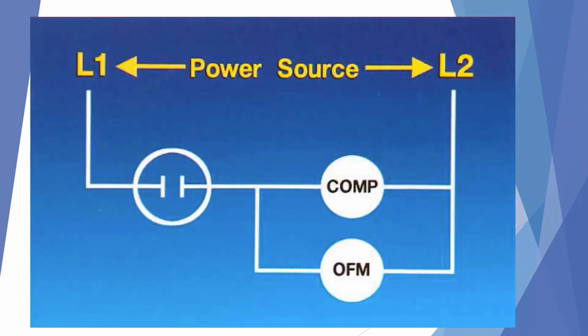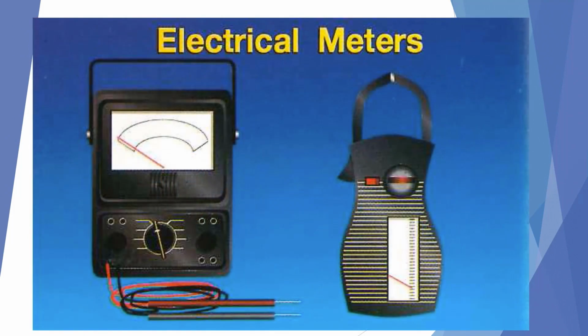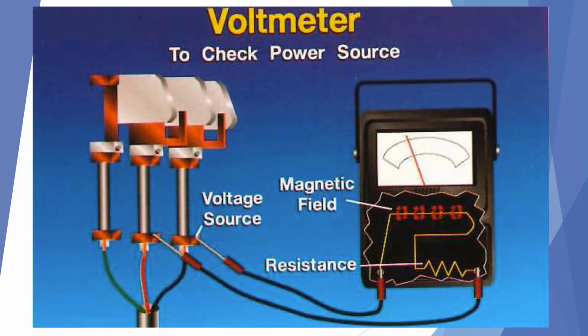The first thing that you need to check on any system is the incoming power source to L1, L2. Every HVAC system has a minimum and a maximum power source that is supplied to the unit. Make sure the power coming into the unit is within the parameters that's listed on the data tag. In order to take these electrical readings on an HVAC system, you will need good quality electrical meters to measure voltage and amp draw on a system. As we stated, you want to take your voltmeter to check the power source to make sure that the correct voltage is being supplied to the unit.